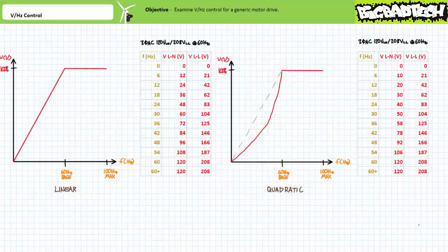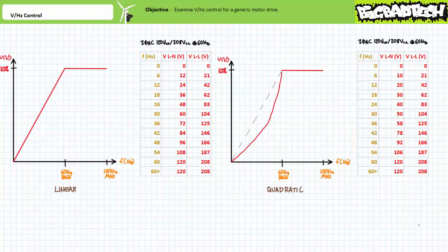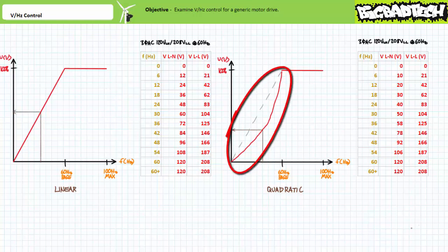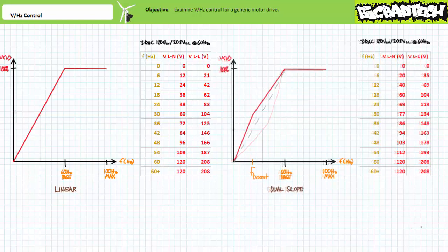Linear volts per hertz control is not the only volts per hertz profile available. For example, consider a reduced torque application where the volts per hertz profile is, for lack of a better descriptive term, a concave quadratic. At the base frequency and up to maximum, full voltage is still applied. However, for excitation frequency conditions below the base frequency, less voltage is applied than with the previous linear volts per hertz method. Such a volts per hertz profile could be used for an application that really needs a gentle start.